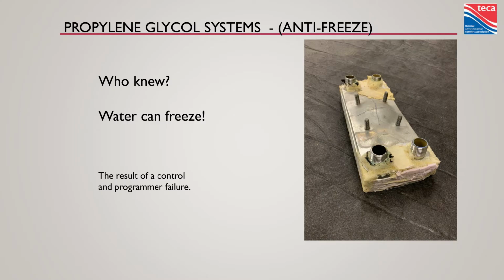So something else to note is chilled water cooling. I talked about monoblocks, I talked about splits. Somewhere you're going to use glycol in both applications is chilled water cooling. The temperature inside that heat exchanger is cooler than your leaving water temperature, and all it takes is a pump to decide, you know what, today was my last good day of service, and suddenly the water in that heat exchanger freezes. That heat exchanger's toast, probably the compressor too. That is a very expensive bill. Add some glycol, you're protected. So any chilled water cooling application should be using glycol as well.